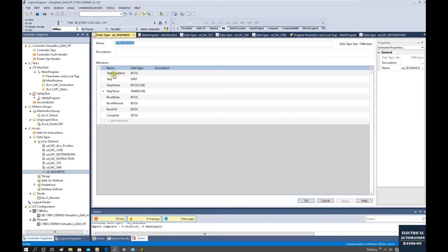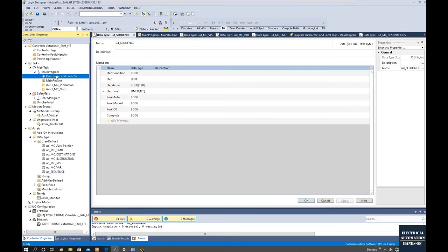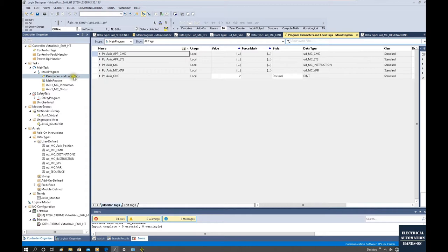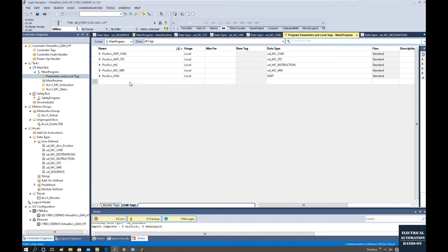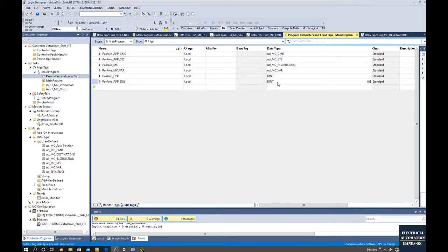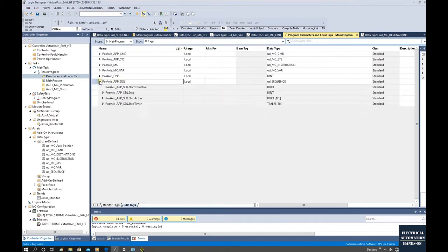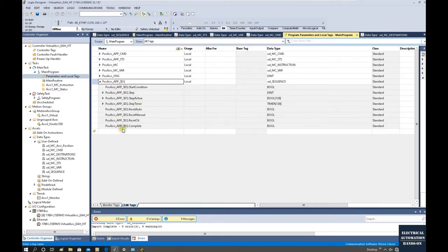From this sequence data type, I have prepared: start condition, step number, step active, step timer — because for each step we can have a timer — reset auto, reset manual, and complete signal. Let's declare one sequence data variable based on this UD sequence data type. Go to Parameters and Local Tags from the main program and click Edit Tags. From here we can declare it, setting the data type to UD sequence. Once we declare this variable and expand it, all those sub-variables can be seen.